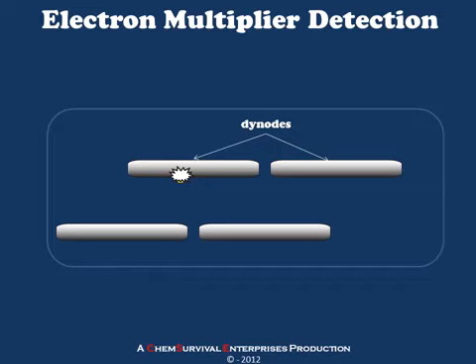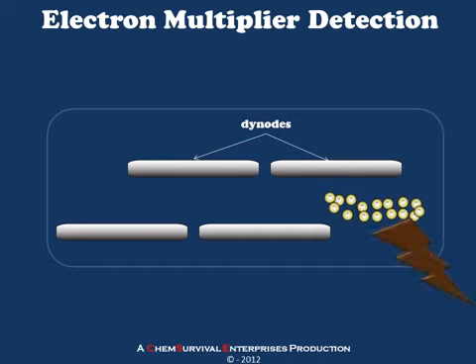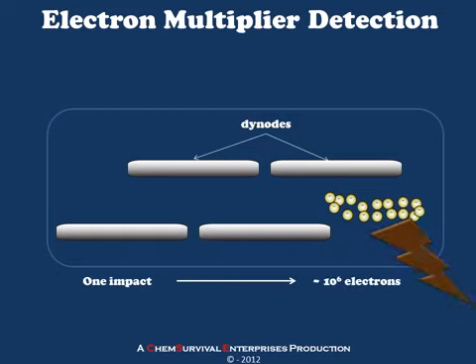This electron traverses the electron multiplier assembly and strikes another dynode. In this case, we're going to produce three electrons per impact. So our three electrons move to the next dynode where a new impact creates three more per electron for a total of nine, and then a new set of impacts creates even more. Very quickly, a measurable amount of current is generated. Within the instrument, about a million electrons are generated per impact in a well-tuned electron multiplier. This means it only takes a few impacts to generate enough electrical current for the workstation computer to read as a signal from the detector.